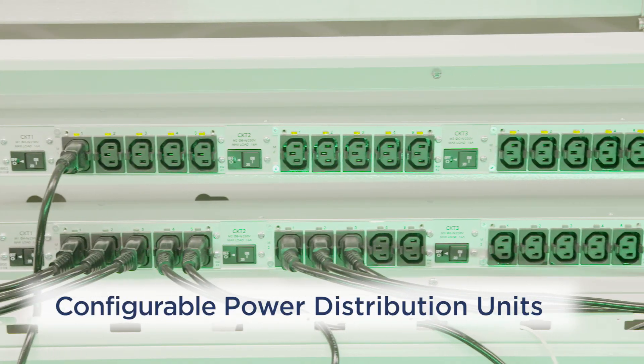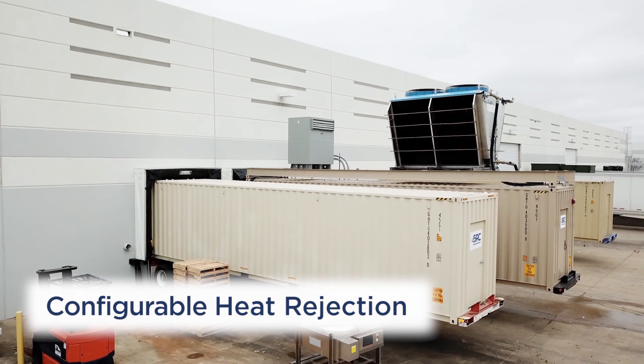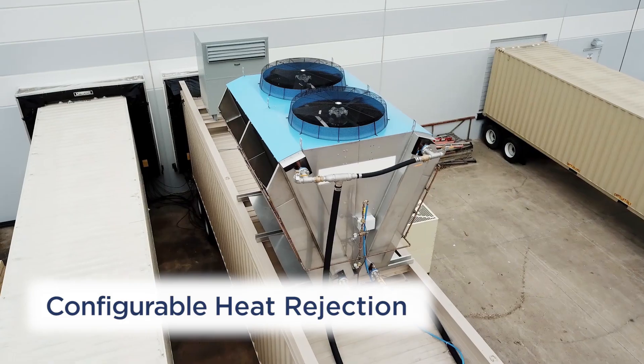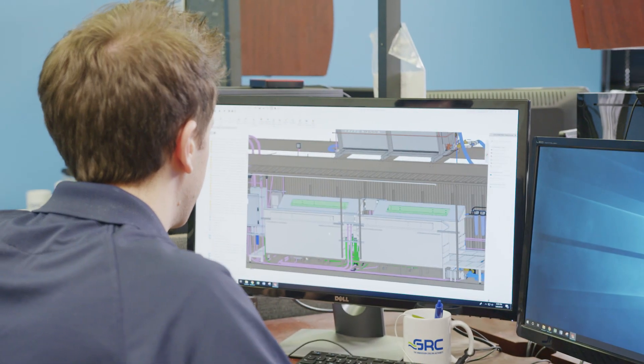We've been building these modular data centers for quite some time, and what that's done for our customers is enabled us to provide a broad range of configurations depending on what the customer's needs are. You can choose whatever rack density you want — 25 to 100 kilowatts — dumb or intelligent PDUs, integrated UPSs or discrete UPS and gensets, multiple ways to reject the heat out of the modular data center, whether that's with traditional evaporative cooling towers, a dry cooler, or a hybrid cooler. When you can mix and match all of those things it gives you a lot of flexibility to meet your requirements and you can do it in a very cost-effective way.